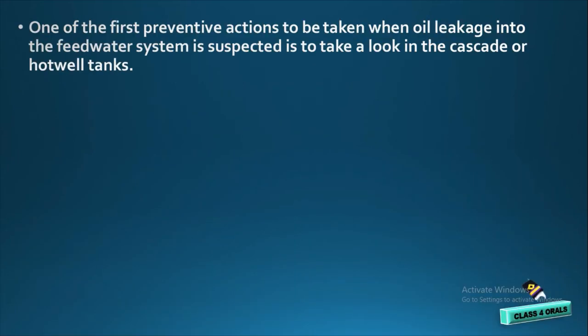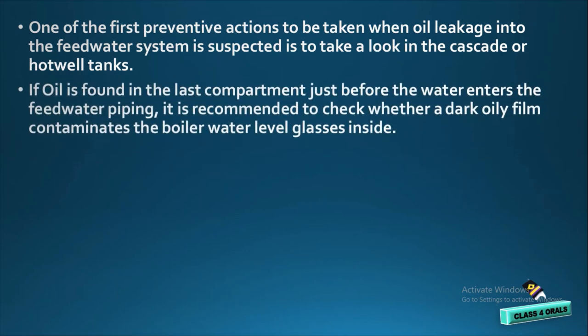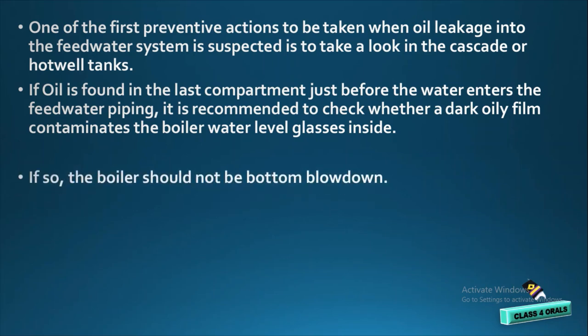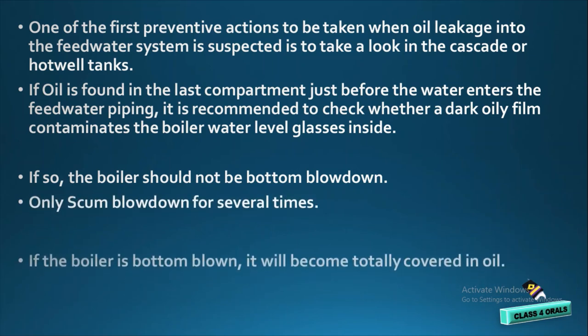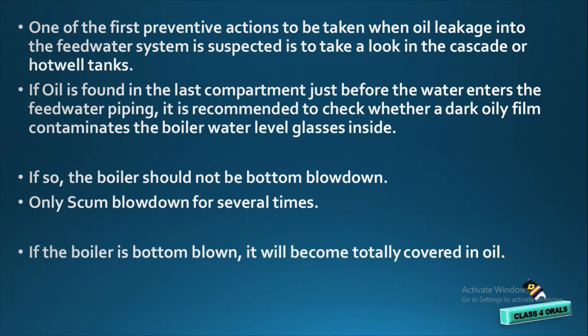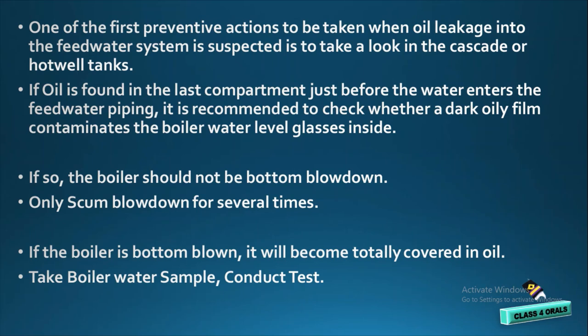One of the first preventive actions to be taken when oil is leaking into the feed water system is to look at the cascade or hot well tanks. If oil is found in the last compartment of the hot well just before the feed water system, it is recommended to check the boiler water gauge glass to see whether oil is present there or not. If there is oil, then we should not do the bottom blowdown — we have to do only the scum blowdown of the boiler several times, otherwise the boiler will be completely covered in oil. Next, we have to take the boiler water sample and perform the water sample test.